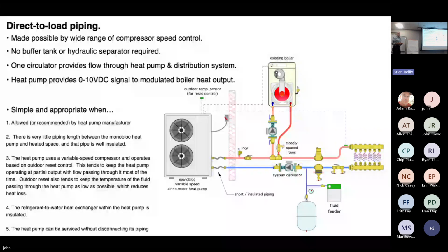I guess what's interesting, John, is you were saying with the monoblocks, a lot of the proprietary controls are in there, but they couldn't really have a pressure relief valve, because if it was zero out and the thing blew, it would just freeze in place. It wouldn't actually discharge. Yeah. The pressure relief valve would typically be inside. And some of the products, like the hydro splits, as well as the DX split systems, they'll put the pressure relief valve inside. Inside? It's inside, yep. Just like a boiler. Yep. But this whole system would have to operate on a solution of propylene glycol and water.